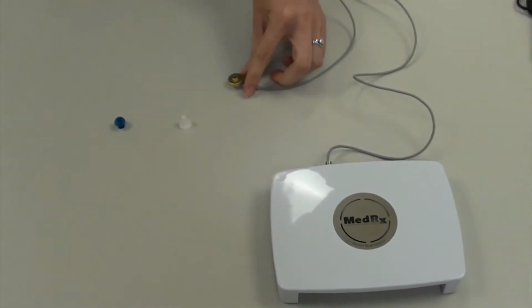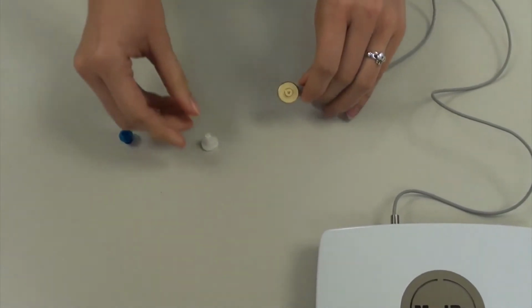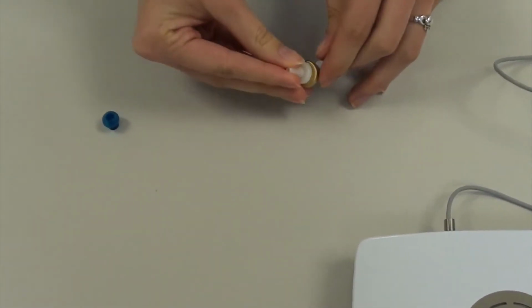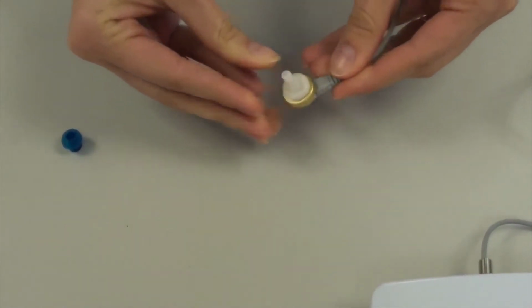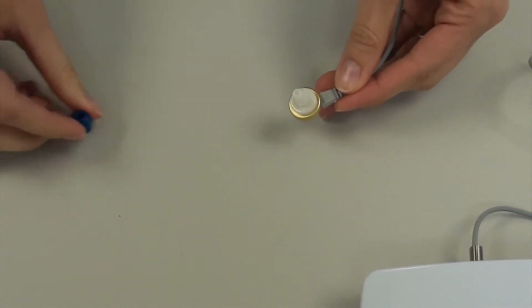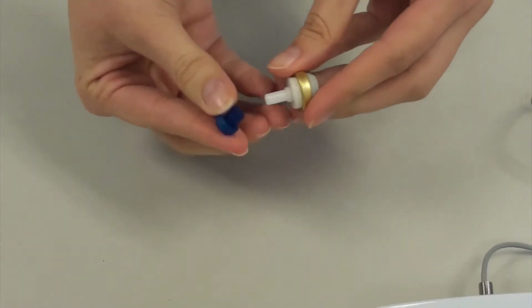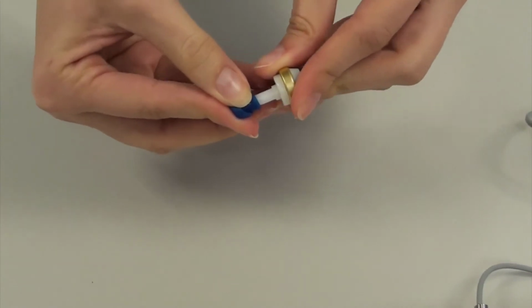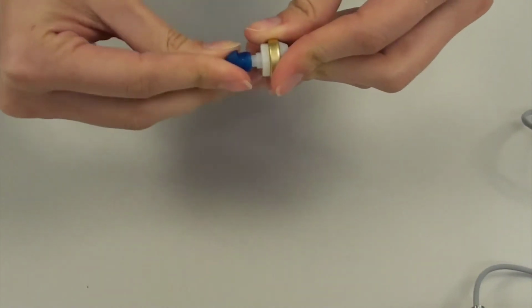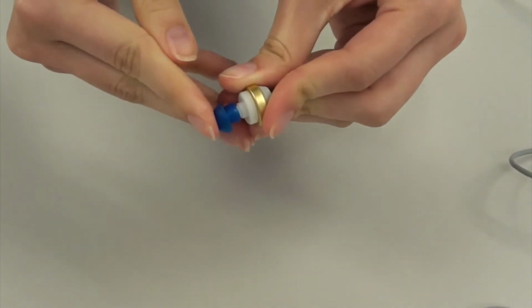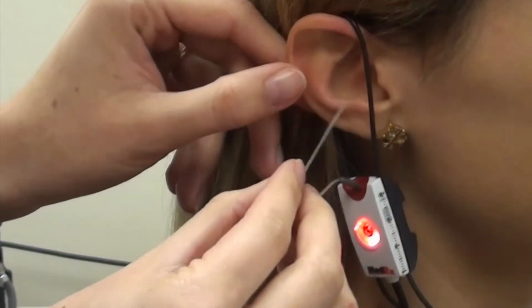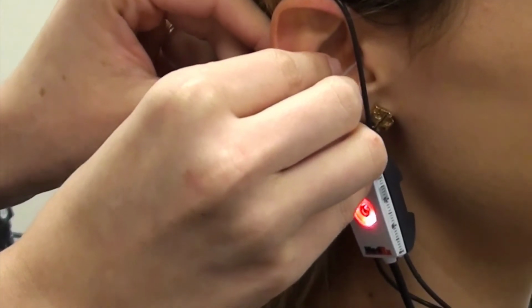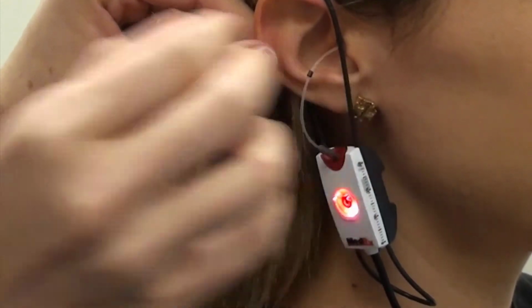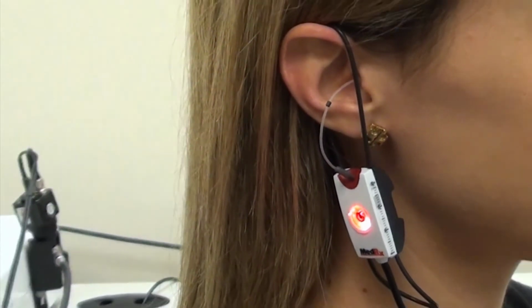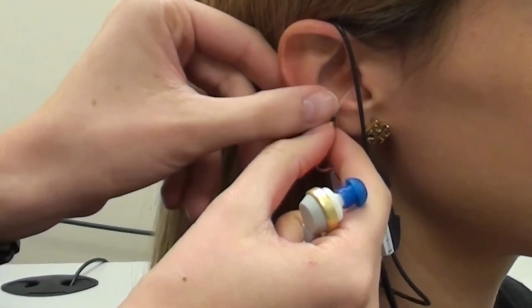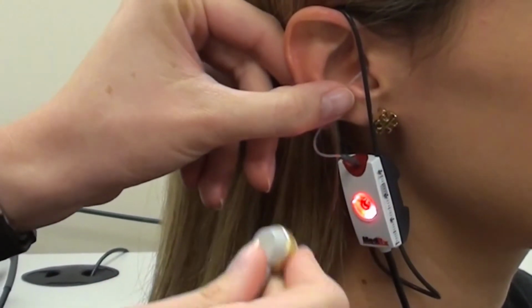Place the white ear tip on the end of the button receiver and attach a disposable ear tip of the appropriate size. Place the probe microphone tube as for all real ear measurements. Next, place the button receiver with the ear tip attachment into the ear.